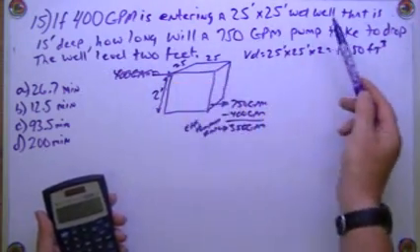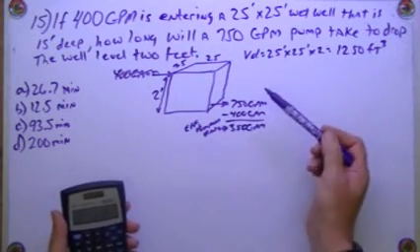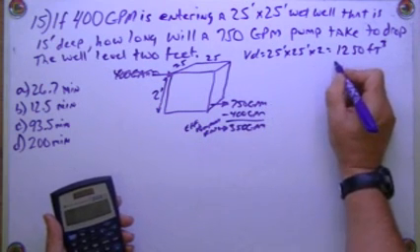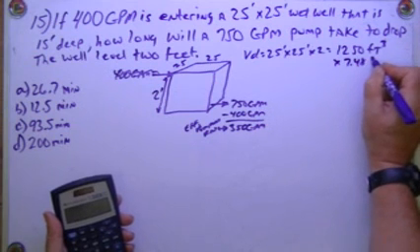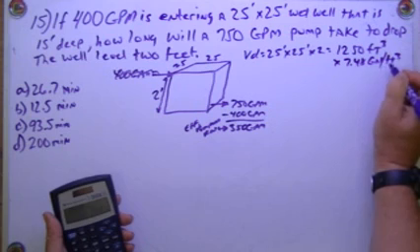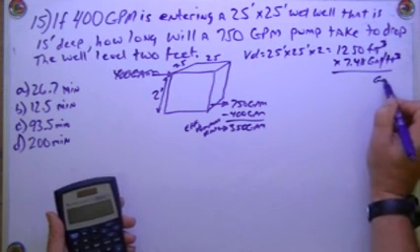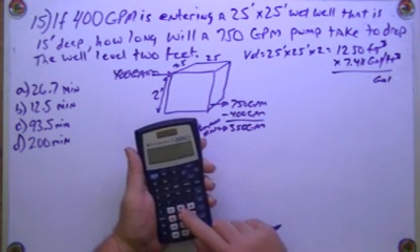We're going to turn it into gallons because we've got gallons per minute on the pump. So that's going to give us the units we want. So I'm going to take 1250 times 7.48 gallons per foot cubed. The foot cubed will cancel out and I'm going to end up with gallons. So 1250 is there in the calculator times 7.48.